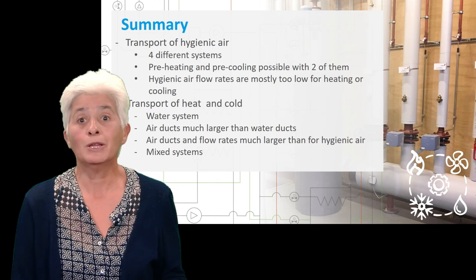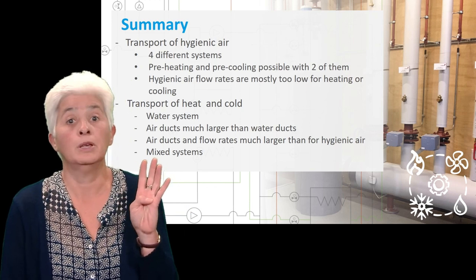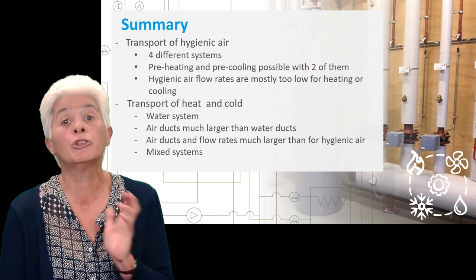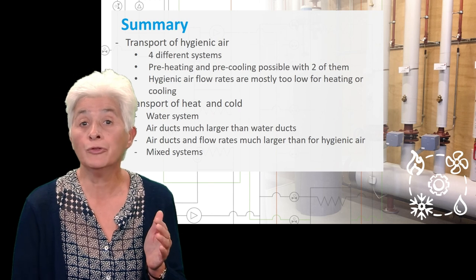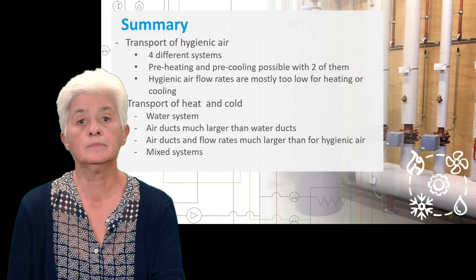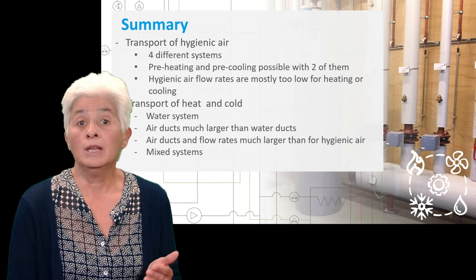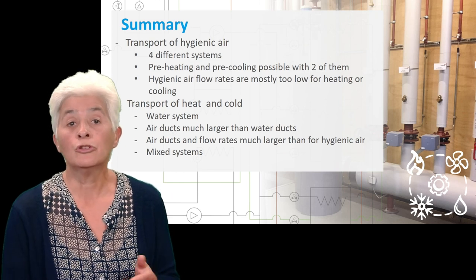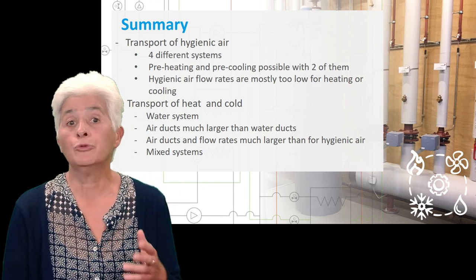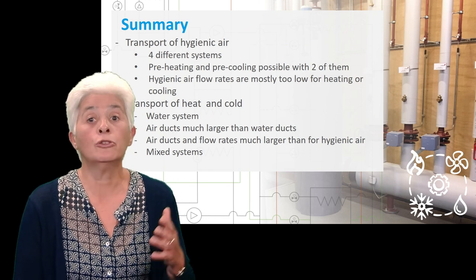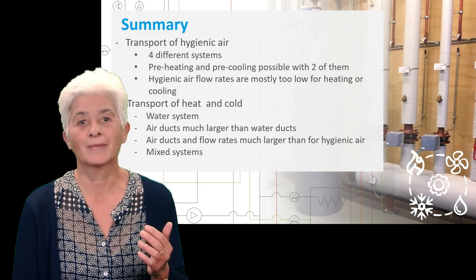Summarizing: you must make a difference between the transport of hygienic air and the transport of heat and cold. For hygienic air, four systems can be used, and only two — mechanical supply and mechanical supply with exhaust — allow for preheating or pre-cooling. In most cases, flow rates of hygienic air are not enough to fully heat or cool a building. Heating and cooling can be done by a water system or by an air system with large quantities of warm or cold air; the ducts with an air system are much larger than with a water system. Very often a mixed system is used, taking advantage of both. Thank you for listening, goodbye!